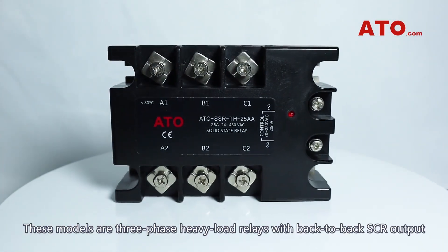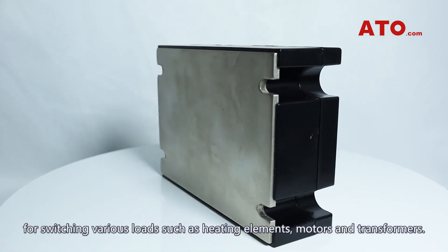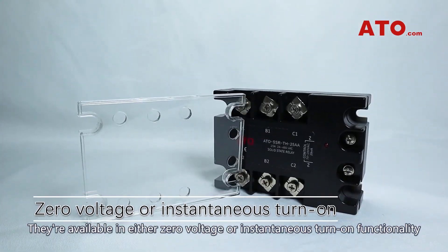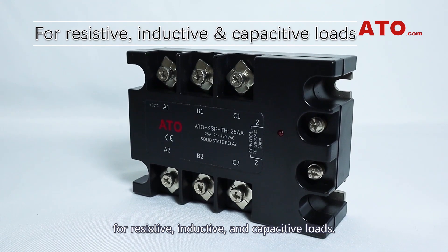These models are 3-phase heavy load relays with back-to-back SCR output for switching various loads such as heating elements, motors, and transformers. They're available in either zero-voltage or instantaneous turn-on functionality for resistive, inductive, and capacitive loads.